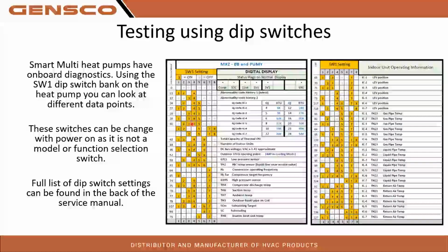Depending on how you set those dip switches, like I said, you can look at different stuff. So if I'm seeing, for example, a 7102 error code, very commonly we see that one, like I mentioned, for overconnected or underconnected. One of the first things I'll do is come over to SW1 with power on and flip on switches 3, 4, and 6, and my LCD display will tell me how many indoor units that heat pump is seeing. So if I see a 7102 and I flip these switches on, I know I have 5 heads on the system.